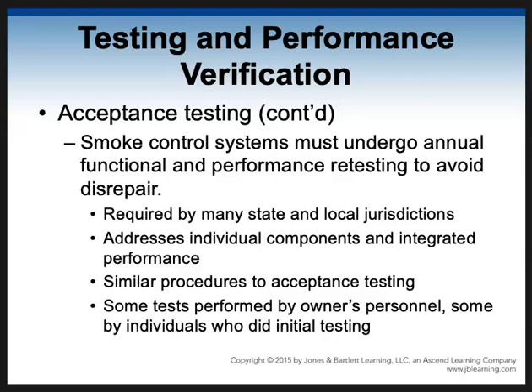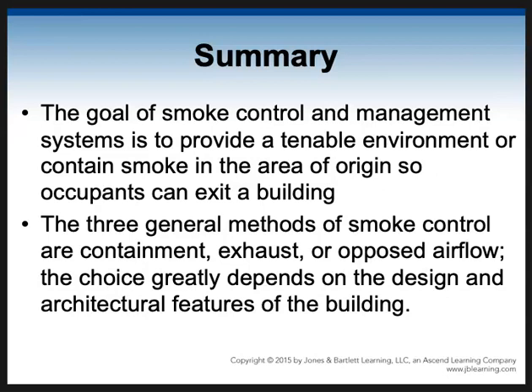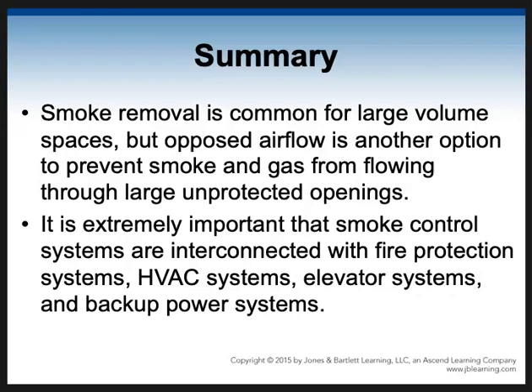So let's go through. You can turn it off here if you don't want the summary. I got 3 little slides on summary, and then we're done. The goal of smoke control and management systems is to provide a tenable environment, giving more time for occupants to exit the building and get out without being subject to the smoke and gases. The 3 general methods are containment, exhaust, pulling it out, or opposed airflow, pushing fresh air in, so pulling and pushing, containing. The choice is going to depend on the engineer and the design and architectural features of the building. It's common for large volume spaces, and we talked about atriums, high-rise, amusement buildings, I3s, things of this nature are where you're going to see a lot of smoke control systems.